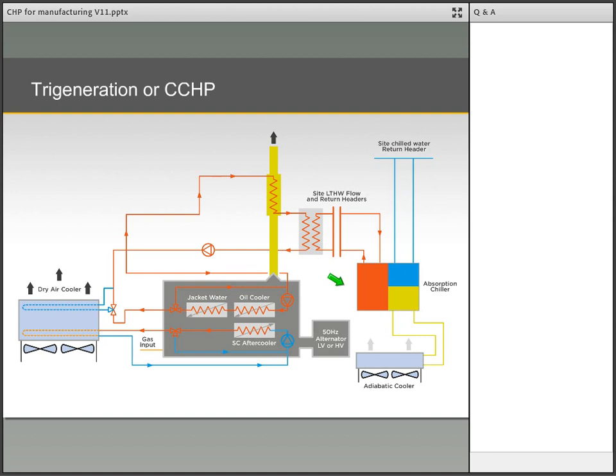The attached slide shows an LTHW fired absorption chiller utilising the site LTHW distribution system. This setup allows the CHP heat output to be easily utilised as both heat and cooling depending on the site requirements. More modern double effect chillers can use the engine exhaust gases directly into the chiller with a boost provided by the LTHW from the engine water jacket. This setup generally enhances the coefficient of performance of the chiller and hence the overall efficiency of the system. Nigel will now look at the fuel sources we can utilise.